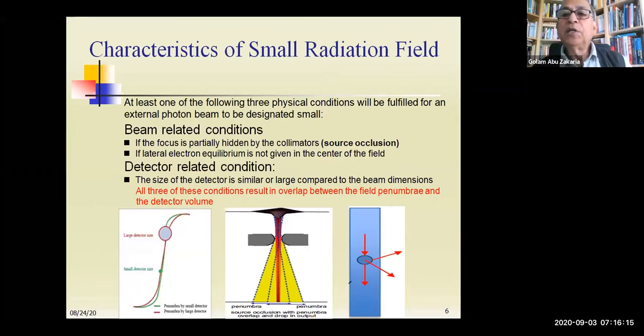So the characteristics of small radiation fields: how can we define small radiation fields? When the following conditions are fulfilled, it is called a small field. The first is a beam related condition, and the second is a detector related condition. What is a beam related condition? If the focus is partially hidden by the collimators, it is called source occlusion. You see in the photos in the middle, you cannot see the whole focus through the collimator. That's why this is source occlusion, and it should be fulfilled by a field which can be called small field dosimetry.